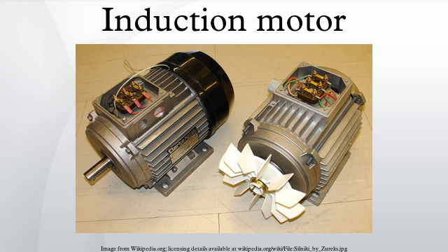Due to Lenz's law, the direction of the magnetic field created will be such as to oppose the change in current through the rotor windings. The cause of induced current in the rotor windings is the rotating stator magnetic field, so to oppose the change in rotor winding currents the rotor will start to rotate in the direction of the rotating stator magnetic field. The rotor accelerates until the magnitude of induced rotor current and torque balances the applied load.